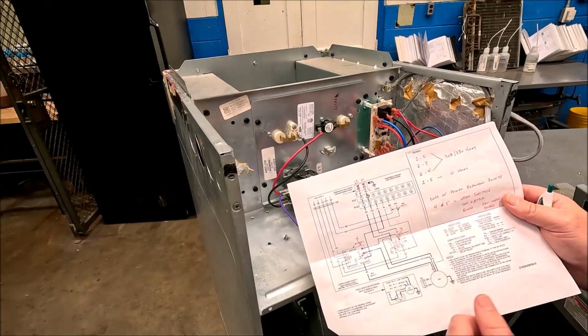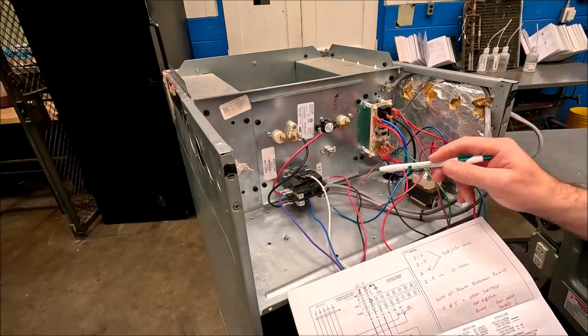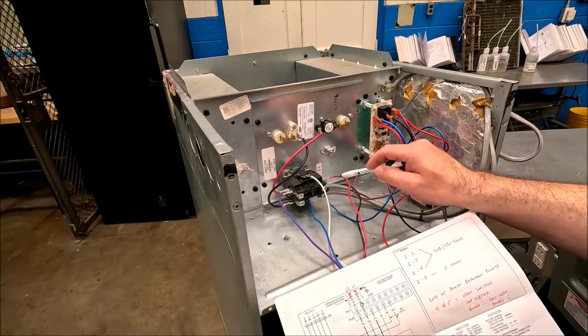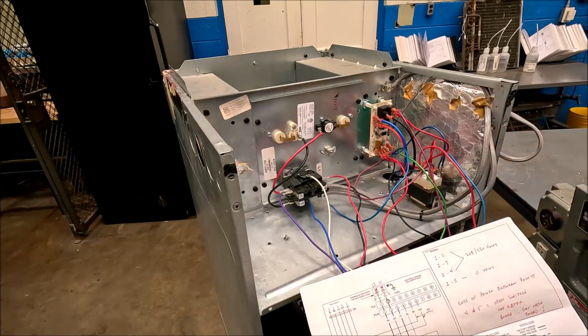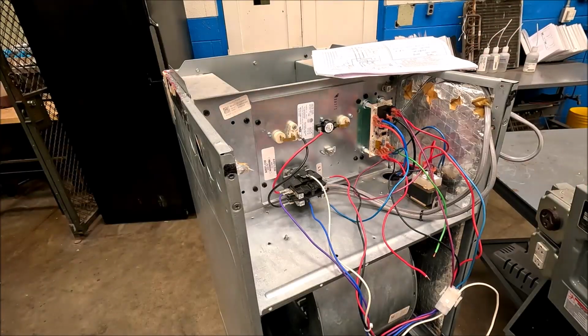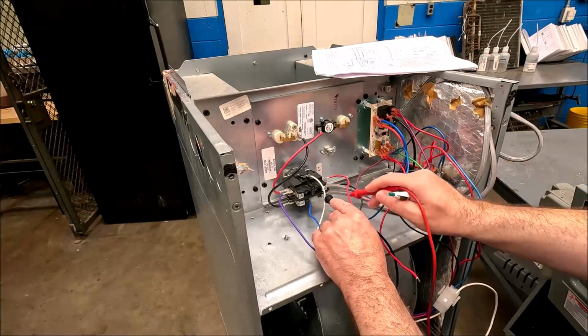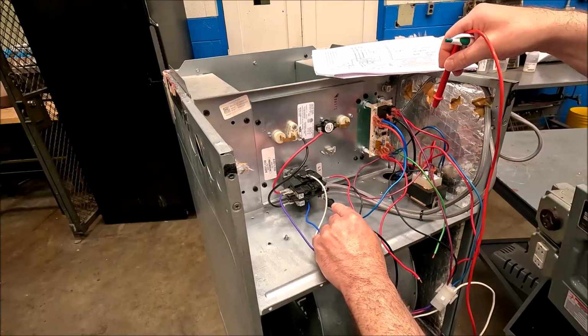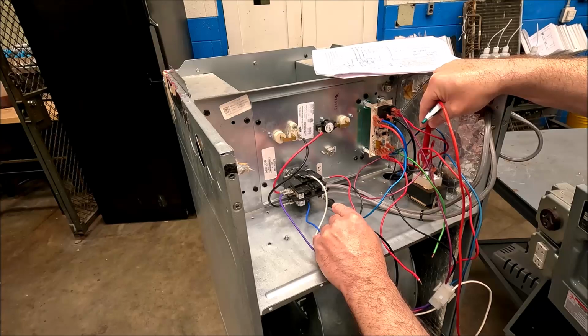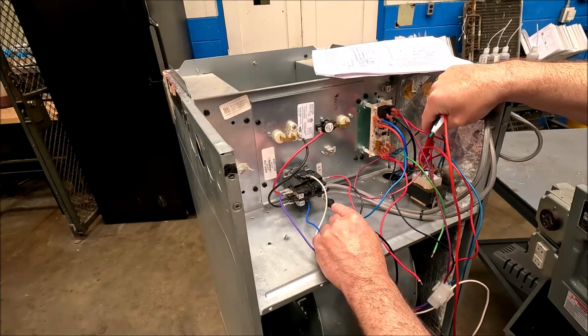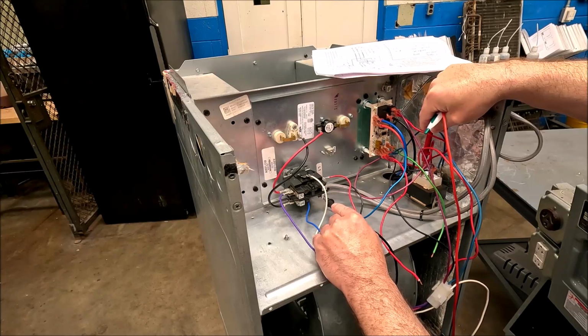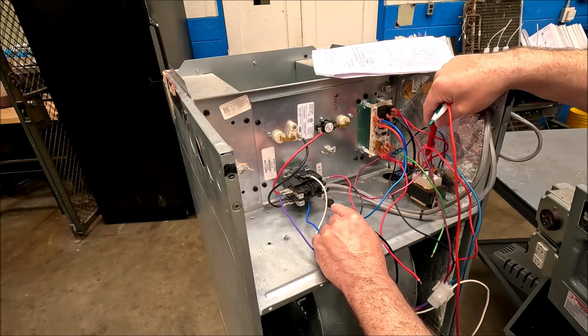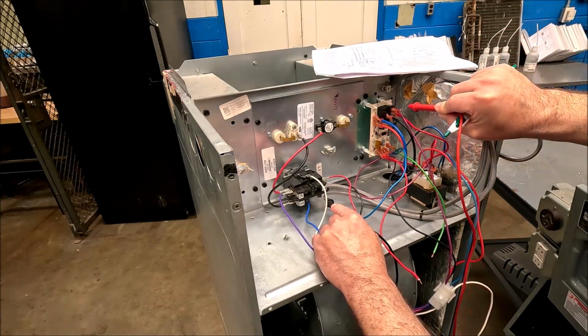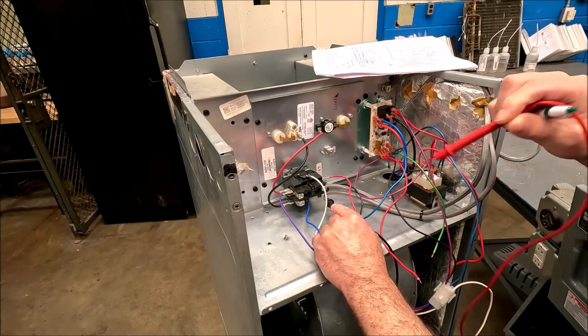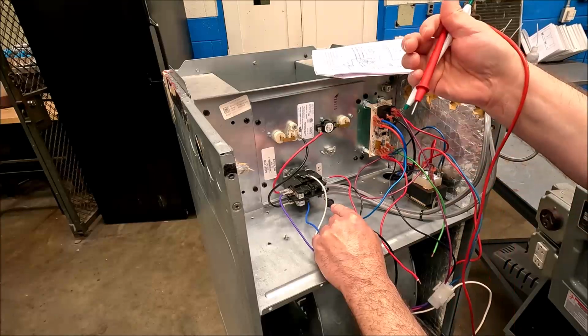But as you go through this, what you'll see is, hey, I've got 1 and 2 here. I'm gonna leave my lead on number 1, which is my other side of power. And then as I leave that here, I'm gonna go to my next point that I've written down. Oh, over at the transformer. Oh, well, I've got 208 or 240 in this case, whatever. Oh, power's still there. So the problem for my blowers not being able to run is I hadn't found it yet. Oh, well, then it jumps over on that red wire up to the relay. So I check in the relay. Or in this case, since it's insulated, I pull the wire off and I check the end of the wire, right?